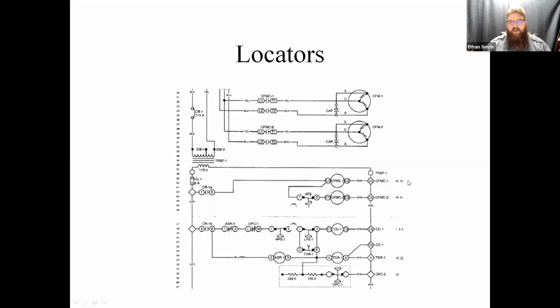but that's what the locator designators are for. Other things you'll find on this diagram and diagrams like it are the wiring designators. They'll either call out colors or numbers, or both. This becomes really useful when you're doing point-to-point testing, because you may have one side of a wire that originates on one end of the unit and the other side that terminates at the other end of the unit. You can test it here, but who knows if that wire is broken somewhere between that compressor and this point here. Inside a rooftop unit, you may have a dozen or two dozen wires all zip tied into a big bundle. It's a giant pain in the butt.